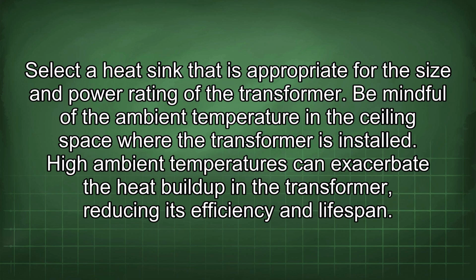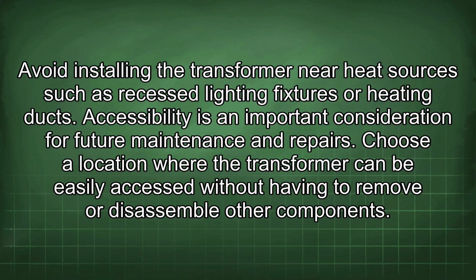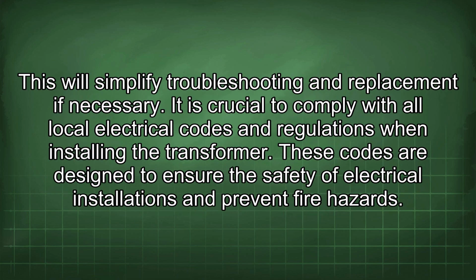Be mindful of the ambient temperature in the ceiling space where the transformer is installed. High ambient temperatures can exacerbate the heat buildup in the transformer, reducing its efficiency and lifespan. Avoid installing the transformer near heat sources such as recessed lighting fixtures or heating ducts. Accessibility is an important consideration for future maintenance and repairs. Choose a location where the transformer can be easily accessed without having to remove or disassemble other components. This will simplify troubleshooting and replacement if necessary.